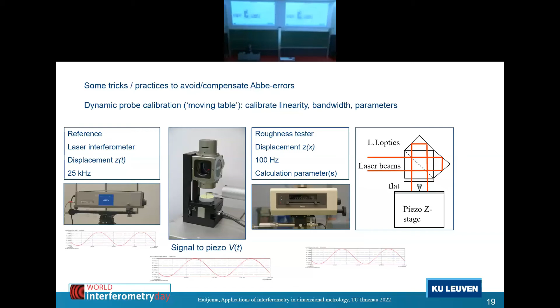And roughness is also measured dynamically because the probe goes up and down all the time. You can simulate this using this piezo, and then you can calibrate different things, such as the linearity. You can calibrate the bandwidth, when the probe stops following this. You can check if parameters are calculated okay, and there are many things you can do. Systems like this are called moving table, and they're very versatile. You can do a lot of things with them.